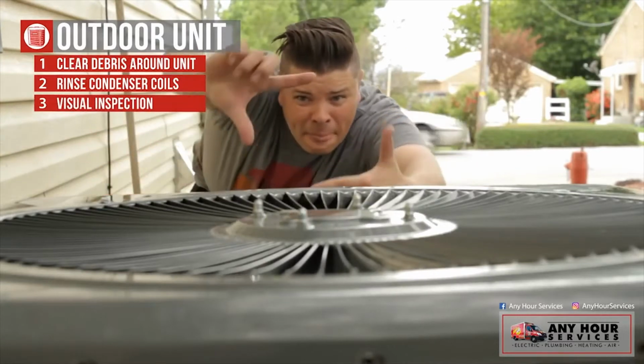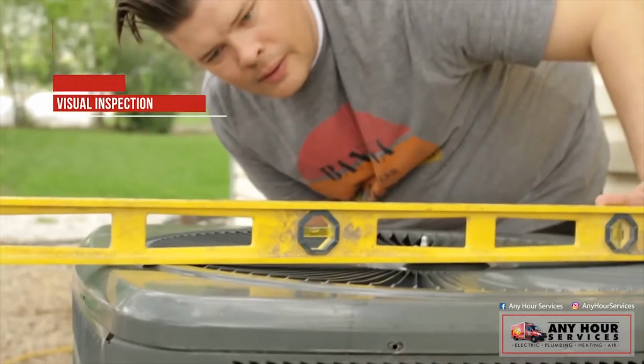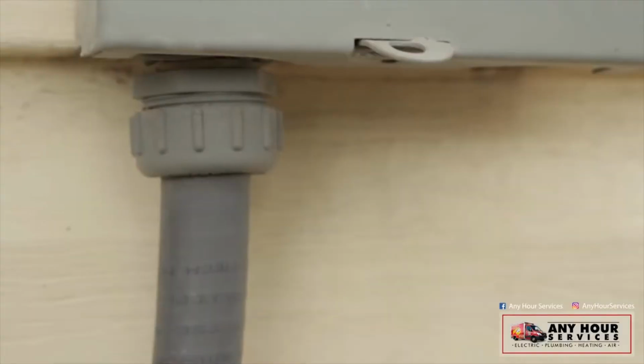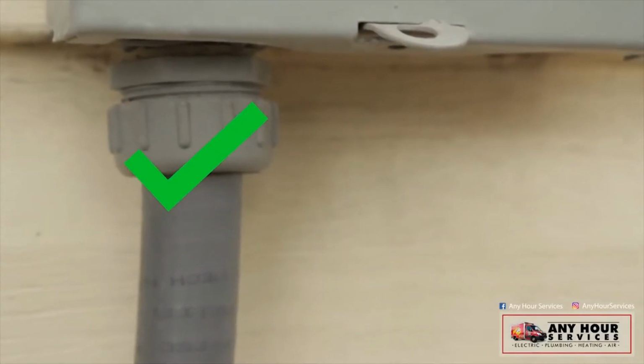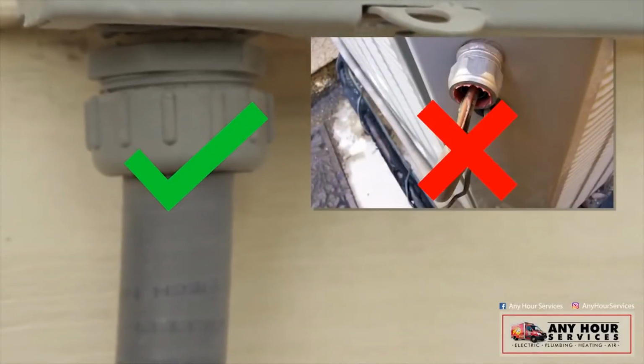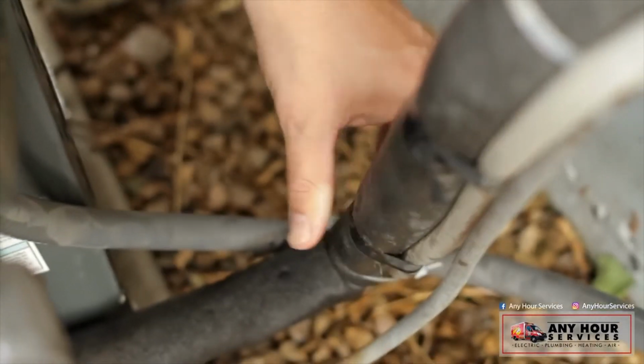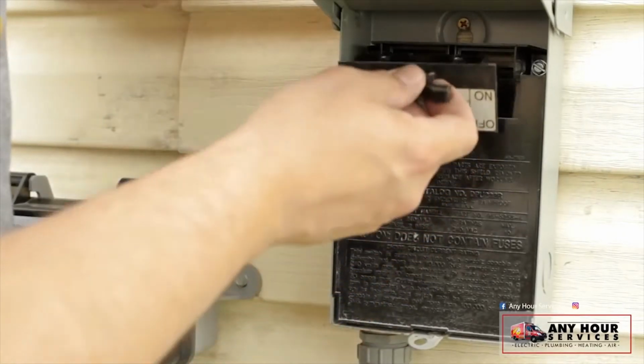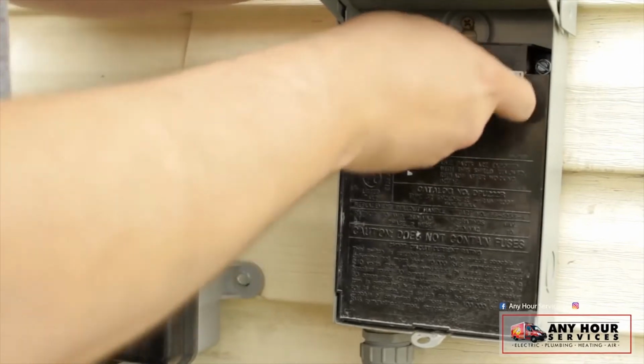See if the unit looks level. If it's too far off center, you may want to have a professional level it up. Check the electrical connections. Make sure that there's no exposed wires. Check the insulation around the line set to make sure it's still good. Now reconnect the power. Careful when you slide the disconnect back into place. You shouldn't have to force it.